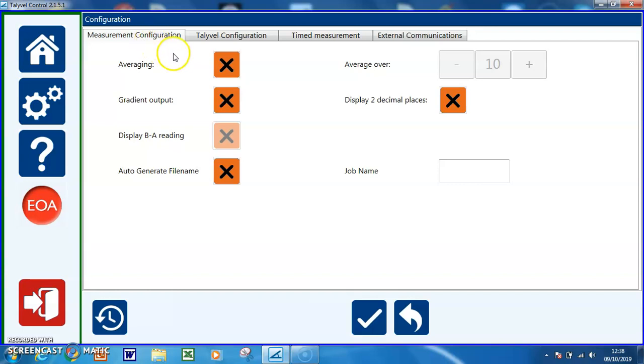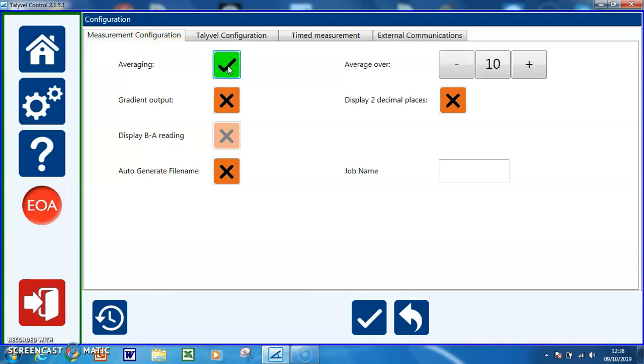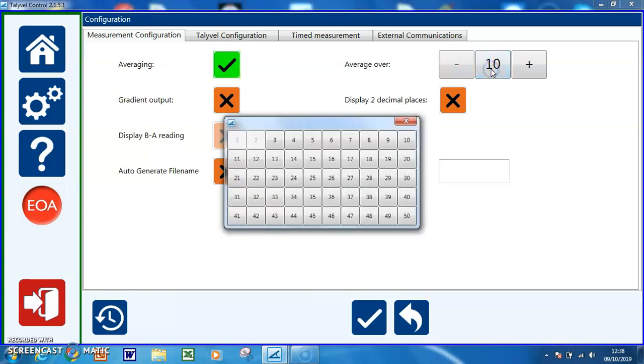There are a number of options. One is averaging. If we set averaging, we can now set the number of points we wish to average over, which can reduce the vibration effect in the background, the background noise.